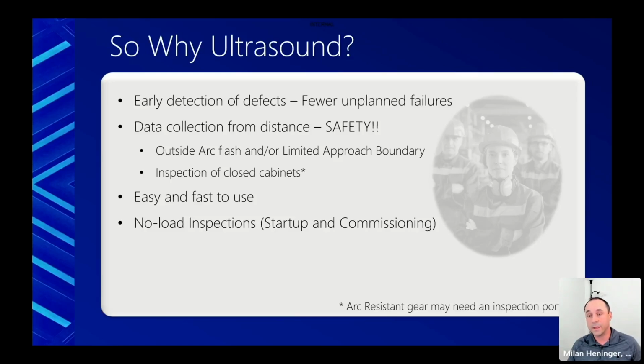The other thing that I really like about it is no load inspections. So the last 3 years, I have commissioned or led the commissioning on about 18 facilities, a little over 5 gigawatts. And we started using ultrasound when I took over the commissioning department in my previous role. What we were able to do was find a lot of these defects while we still had construction teams on site, while we were still working punch list, and we were able to work through those things before we actually put real power to the facility. And that was a huge, huge help because loose connections and broken bushings and things like that were getting caught before we were putting real power to the system, just voltage.